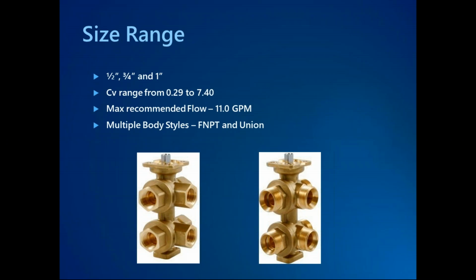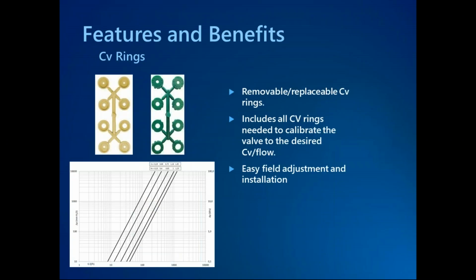One thing to keep in mind is the six-way control valve is first and foremost a control valve. So when we think about traditional control valves in a two-pipe system, we like to have unions bracketing that in the event that it does need to get replaced or field serviced for some reason, because it is the component that's probably moving the most out of any traditional coil kit. So looking at some features and benefits of different six-ways in the market.